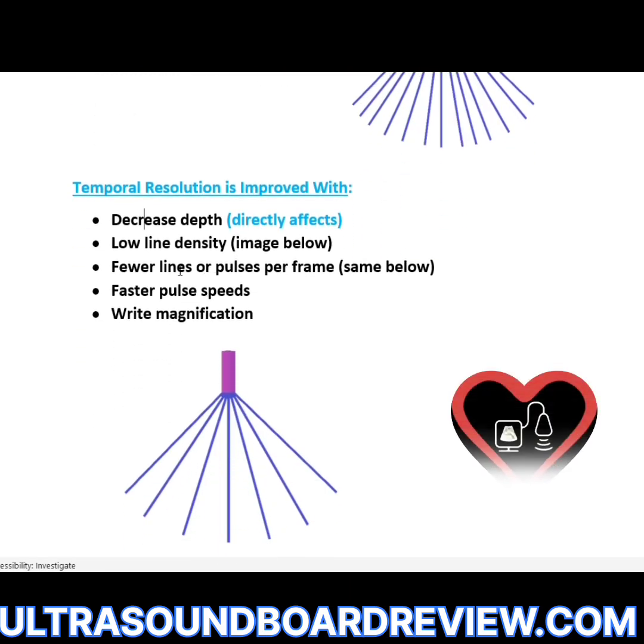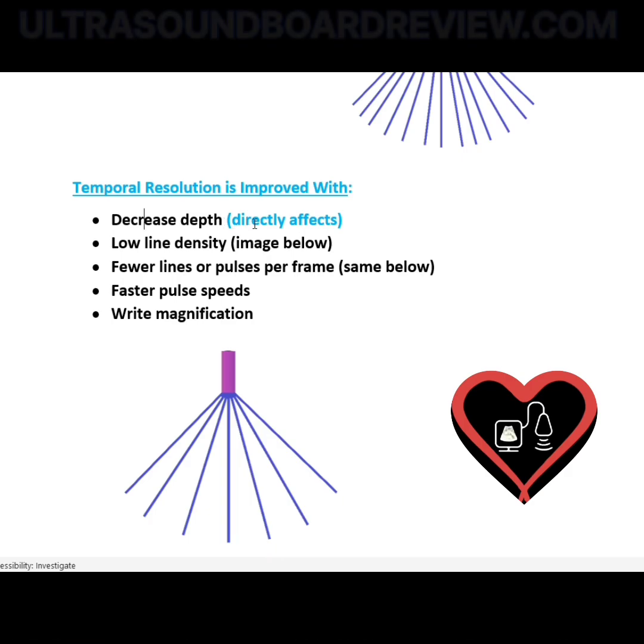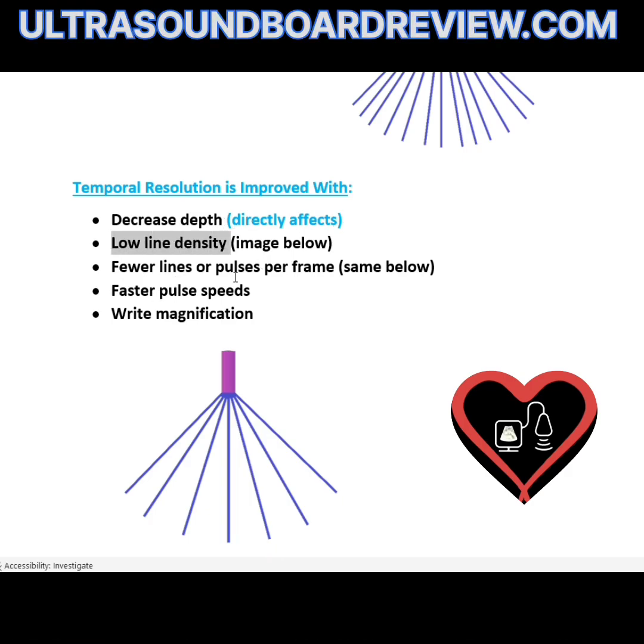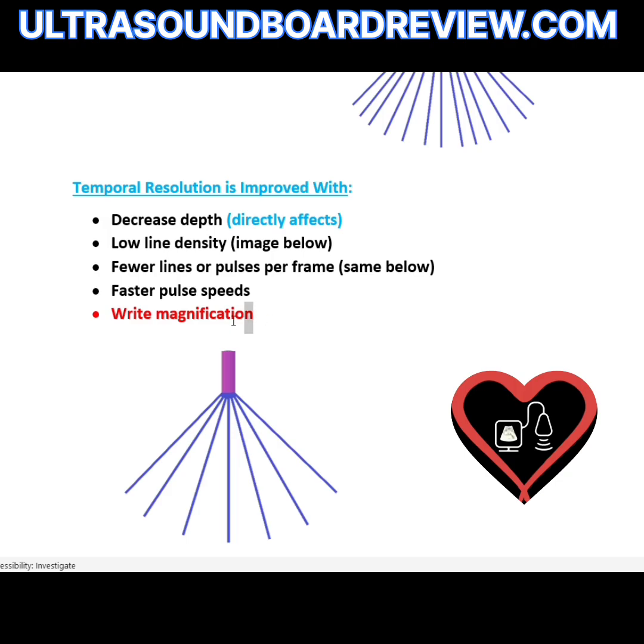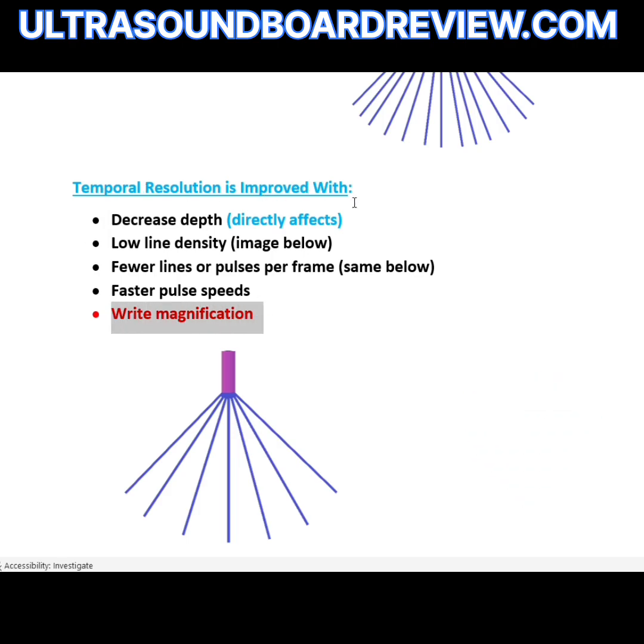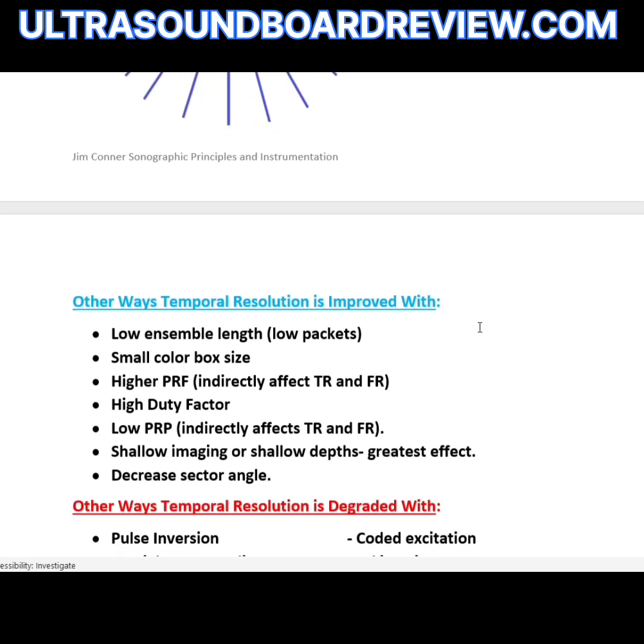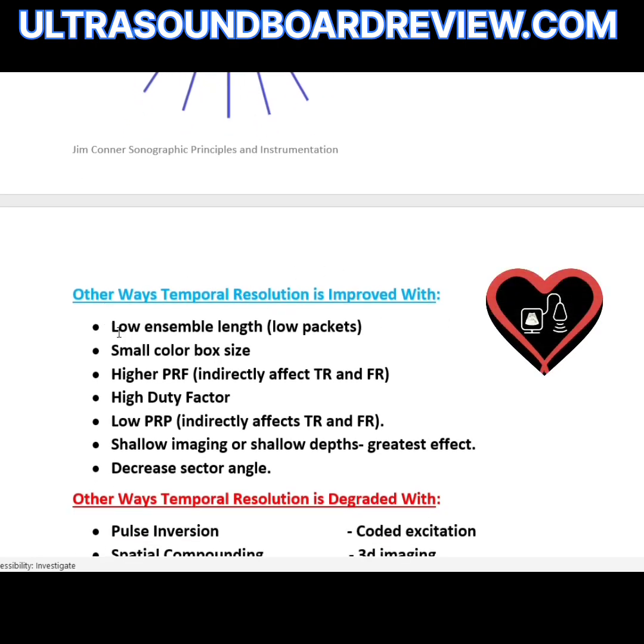Things that improve temporal resolution include: decreasing depth (which directly affects it), low line density, fewer lines or pulses per frame, faster pulse speeds, and write magnification — make sure you remember that write magnification will actually improve temporal resolution. Additional improvements include a low ensemble length or low packets, small color box size, and higher PRF, which indirectly affects temporal resolution and frame rate.